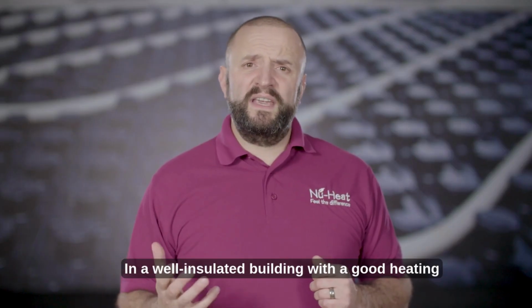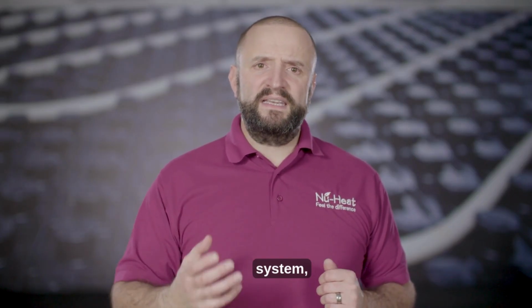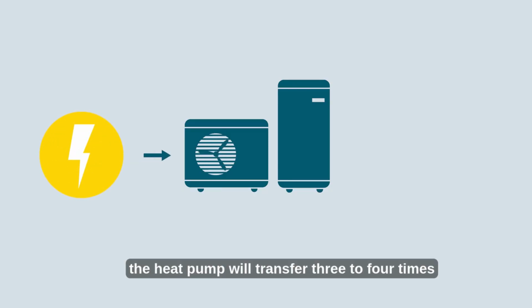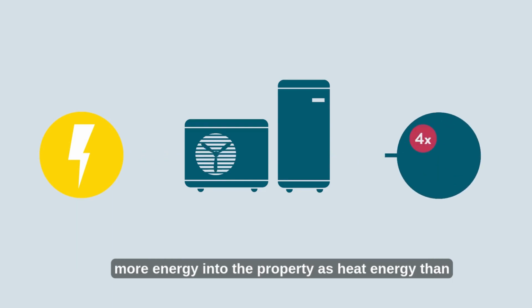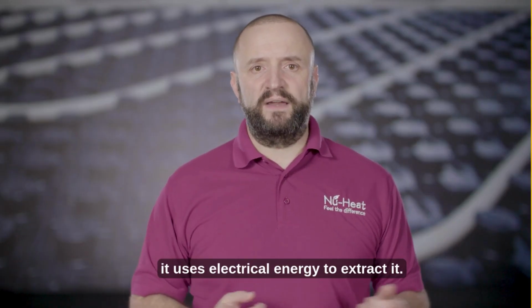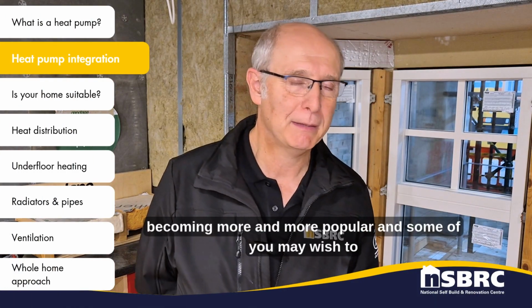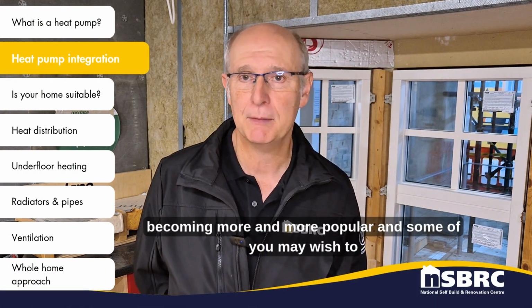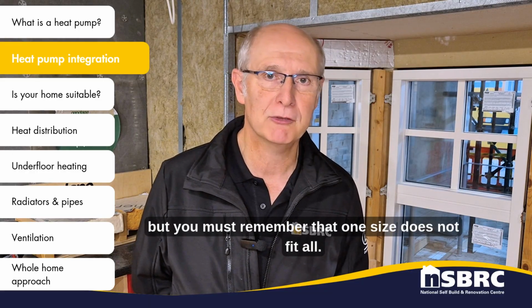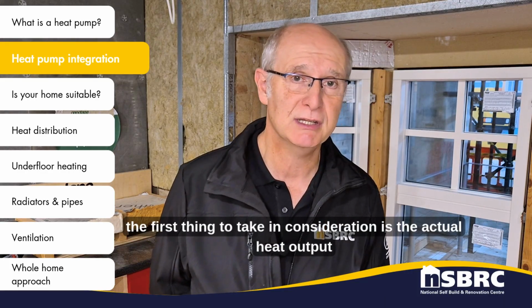In a well-insulated building with a good heating system, the heat pump will transfer 3 to 4 times more energy into the property as heat energy than it uses electrical energy to extract it. Now, heat pumps are becoming more and more popular. It's something you may wish to consider for your project, but you must remember that one size does not fit all. Okay, so the first thing to take into consideration is the actual heat output of that said heat pump.